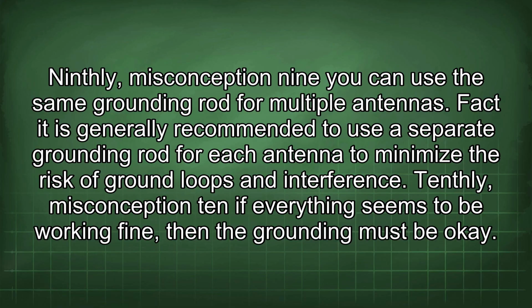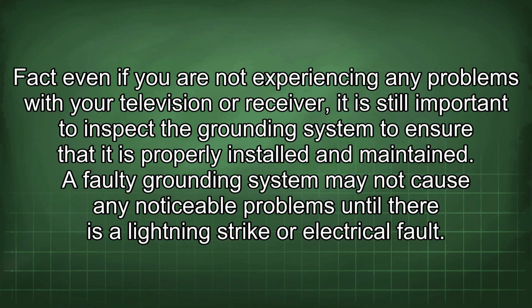Tenthly, misconception 10: if everything seems to be working fine, then the grounding must be okay. Fact: even if you are not experiencing any problems with your television or receiver, it is still important to inspect the grounding system to ensure that it is properly installed and maintained. A faulty grounding system may not cause any noticeable problems until there is a lightning strike or electrical fault.